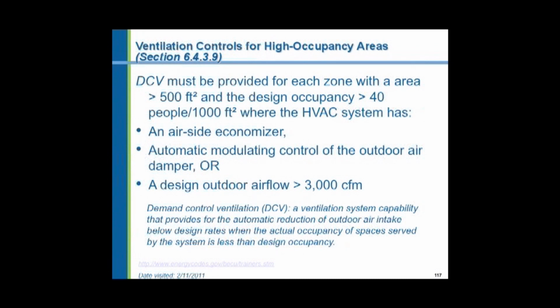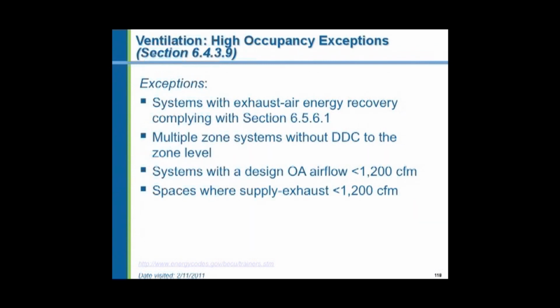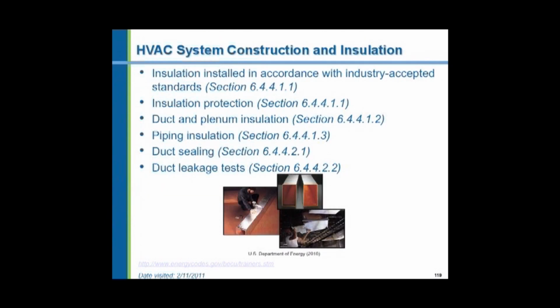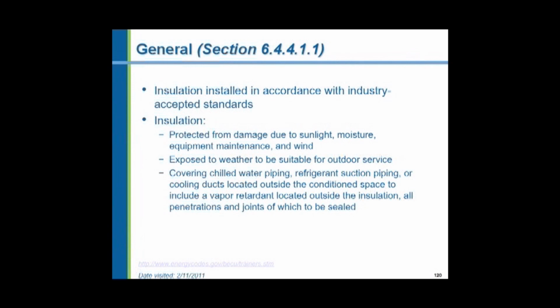So anyway, they want demand-controlled ventilation for areas larger than 500 square feet, more than 40 people per 1,000 square feet, where there's an economizer on the air side, an outside air damper that's modulating, and an airflow greater than 3,000 CFM. There are some exceptions, however. When you're building the ductwork and the piping, they say you have to insulate it, and you have to seal it, and you have to test for leakage. The insulation has to be installed in accordance with the instructions. Protect the insulation. It has to be protected from sunlight. If it's outside insulation, from sunlight, from mechanical damage, from hail damage, from water damage. If it's down near the ground, from lawnmowers and string trimmers.